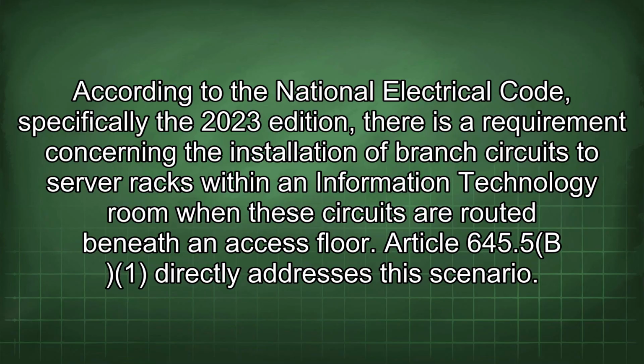According to the National Electrical Code, specifically the 2023 edition, there is a requirement concerning the installation of branch circuits to server racks within an information technology room when these circuits are routed beneath an access floor. Article 645.5 directly addresses this scenario.